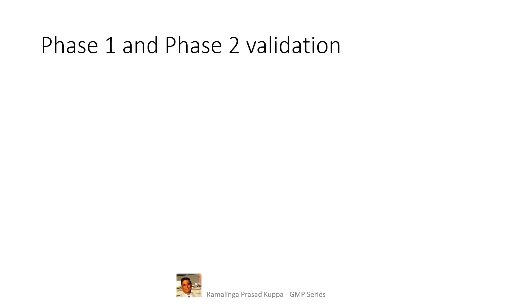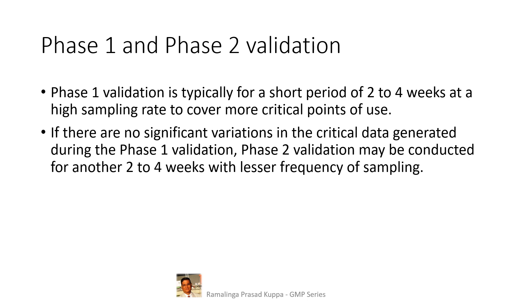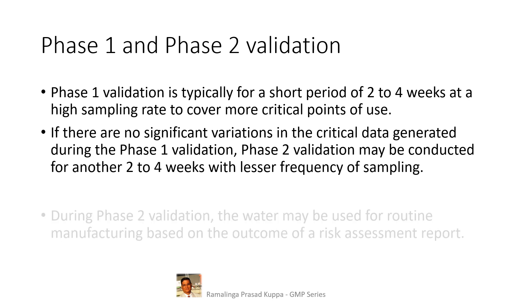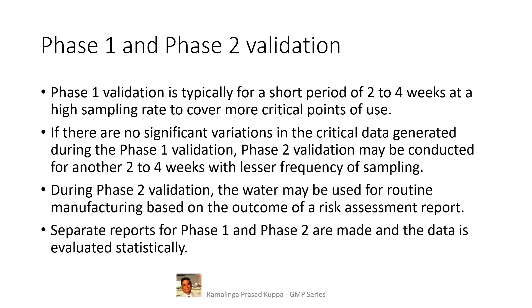The strategy described previously is summarized here. Phase 1 validation is typically for a short period of 2 to 4 weeks at a high sampling rate to cover more critical points of use. If there are no significant variations in the critical data generated during phase 1 validation, phase 2 validation may be conducted for another 2 to 4 weeks with lesser frequency of sampling. During phase 2 validation, water may be used for routine manufacturing based on the outcome of the risk assessment report. Separate reports for phase 1 and phase 2 are made and the data is evaluated statistically.